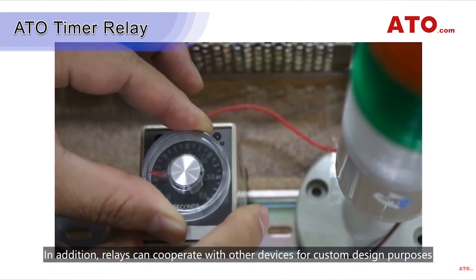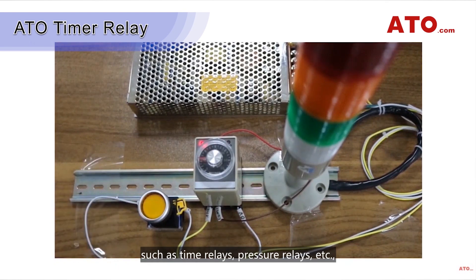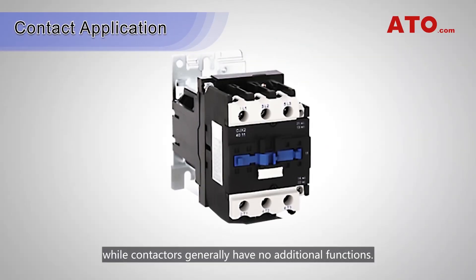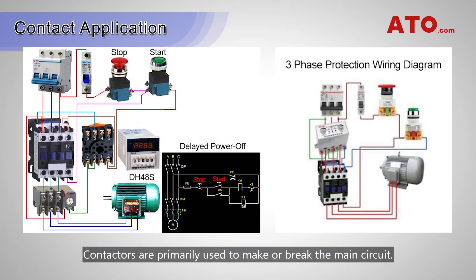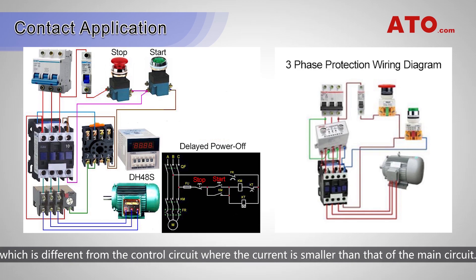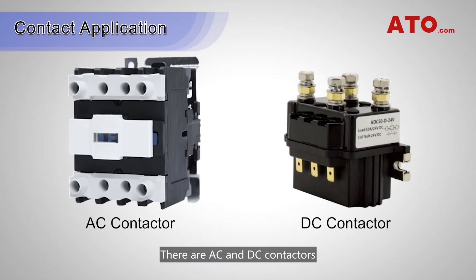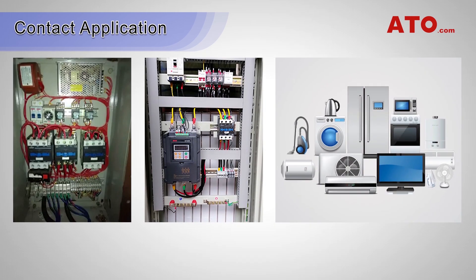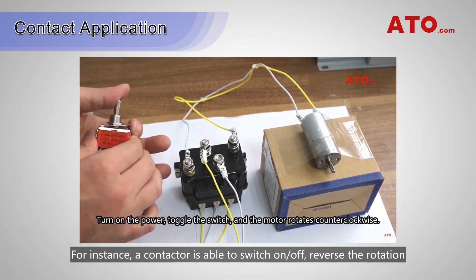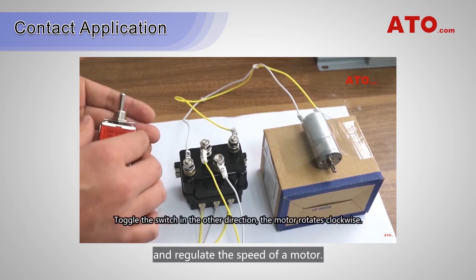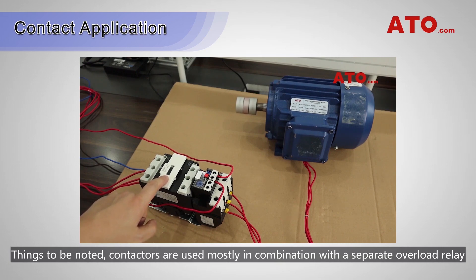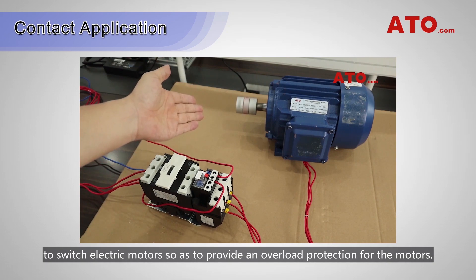In addition, relays can cooperate with other devices for custom design purposes, such as time relays and pressure relays. Contactors, on the other hand, generally have no additional functions and are primarily used to make or break the main circuit. The main circuit works only when it is connected, and carries higher current than the control circuit. There are AC and DC contactors, typically used in electric power, power distribution, and other power consumption situations. For instance, a contactor is able to switch on and off, reverse the rotation, and regulate the speed of a motor. It's worth noting that contactors are mostly used in combination with a separate overload relay to switch electric motors and provide overload protection.